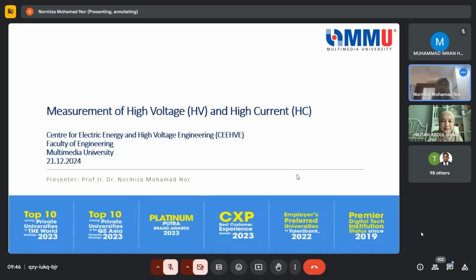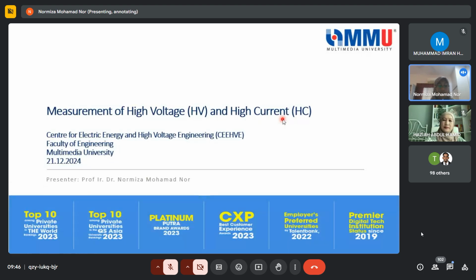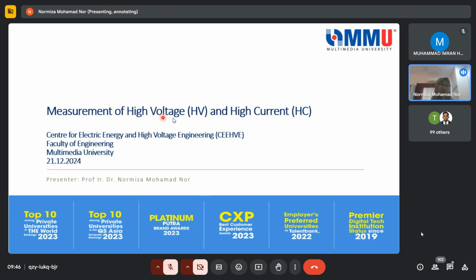All right. Okay, so today we are going to cover the topic, measurement of high voltage and high current. Actually, regarding high current, I can say that in most testing we hardly have this application, except for certain test loops, such as resistive loops like linear resistors or surge arrestors. For that reason, we normally use high current measurement. But of course, for high voltage, for other equipment such as transformers, switchgear, insulators, or cables, the application is high voltage.